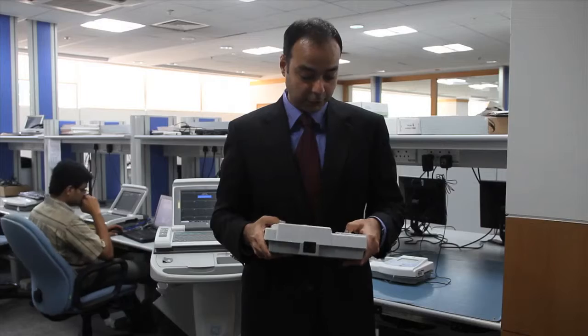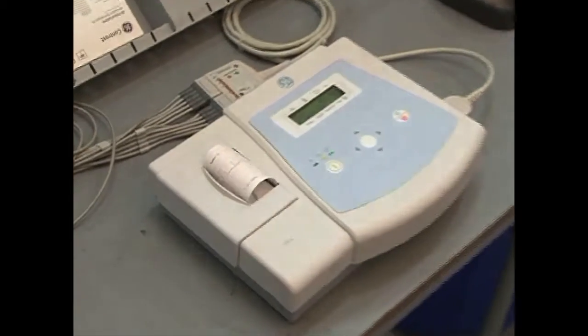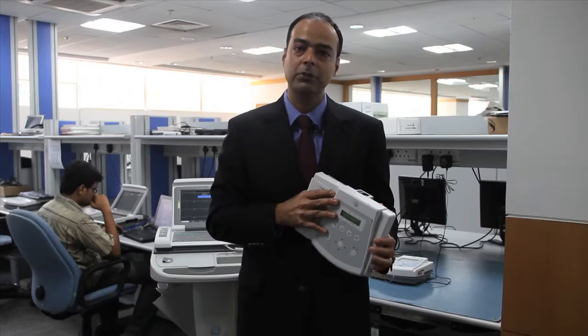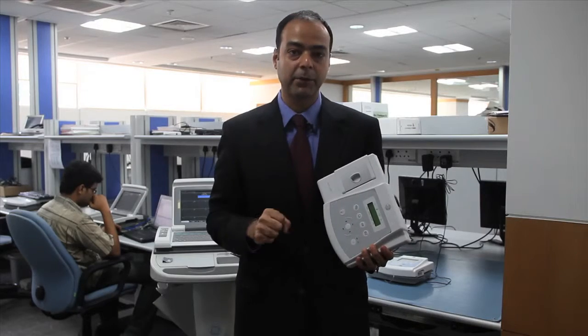We also looked at this printer to actually print the ECG, and we essentially are reusing the printer that's used to print bus tickets in rural India. This gives us the capability to not only make it more robust for the environment, but also leverage spare parts and things that are more easily available in that particular location.